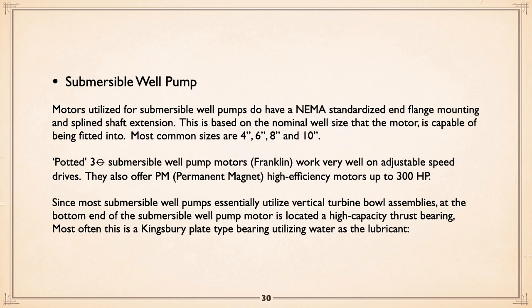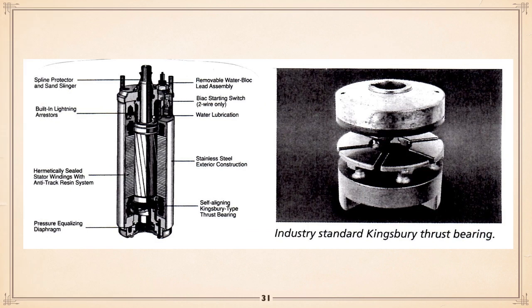It's a Kingsbury, in most cases, a Kingsbury plate type bearing using water as a lube. And here, much like car bearings, the actual engine bearings are not ball bearings in almost all. They're a metal sleeve with oil serving as the lubrication between them. Here, you have a smooth surface and a plate that's allowed to pivot a little bit to adjust. And it's almost like the plate is water skiing. There's water allowed to go right down to the bottom. In fact, these motors are water filled. And those plates will actually form a small surface of water as it turns around. And that's what is actually doing the lubrication. And of course, because it's a fairly large area, they can tolerate a very high thrust.